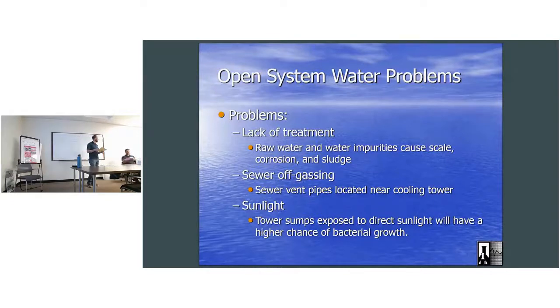Oh yeah. You know the Baltimore air coils, they don't have the fill exposed on the side. It's all enclosed, like on an evaporative condenser. They hardly ever grow anything except maybe up on the top, where sunlight hits. Yeah, you're right. But if you think of the newer Marley ones, it has the fill like this, the little trough here, and you have the big trough back here. Those have a lot of problems, mostly because your sump pump goes over, and all this fill is facing direct sunlight. It all grows on the edges, so your water can look fantastic while the edges are growing crap all over it.